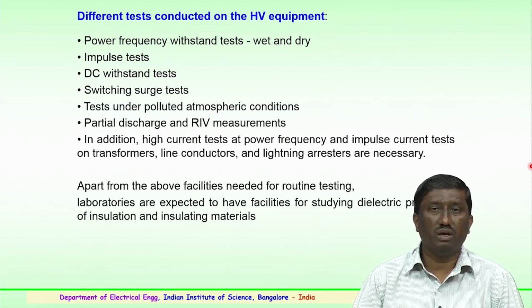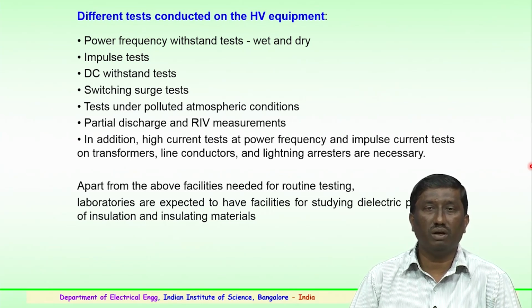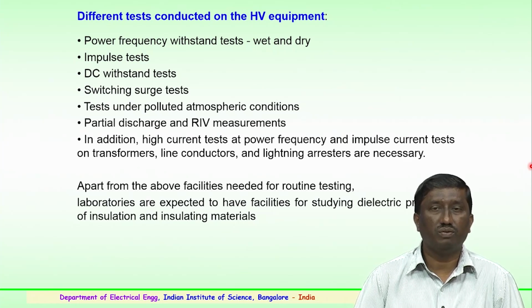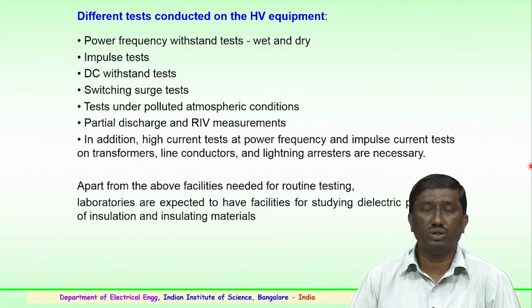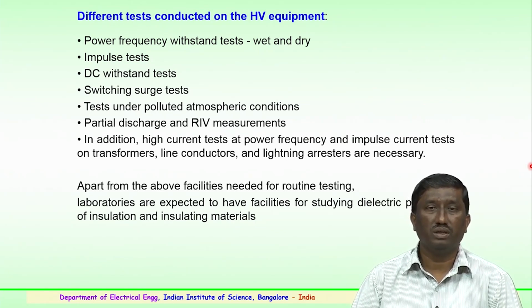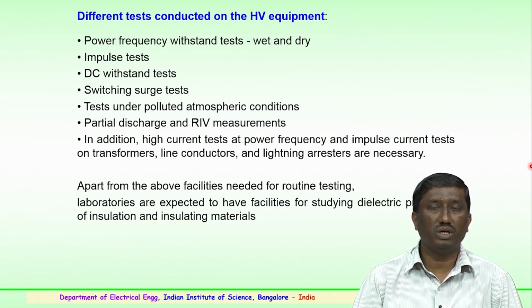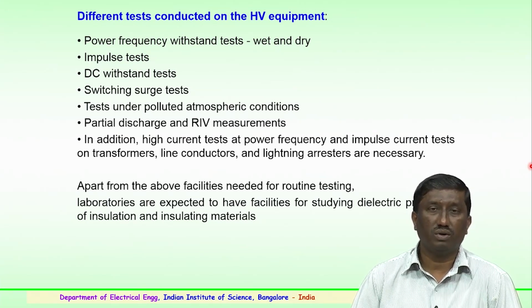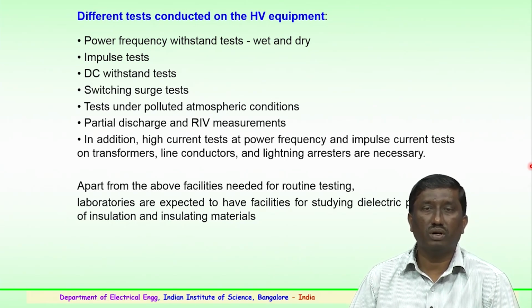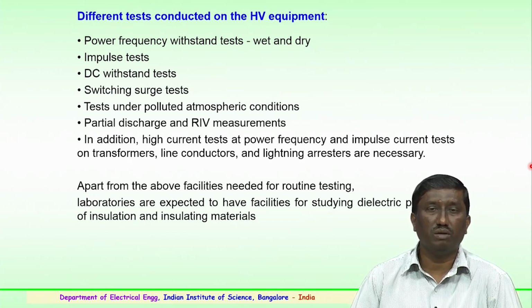So, apart from these tests, tests under polluted or contaminated environments have to be carried out on various types of high voltage equipments. Most of these equipments will be operating in the outdoor environment. So, the contamination or polluted test is essential for the equipment. Apart from the polluted or contaminated test, partial discharge is very important for the cables, transformers and other equipments, which are to be performed in the lab.